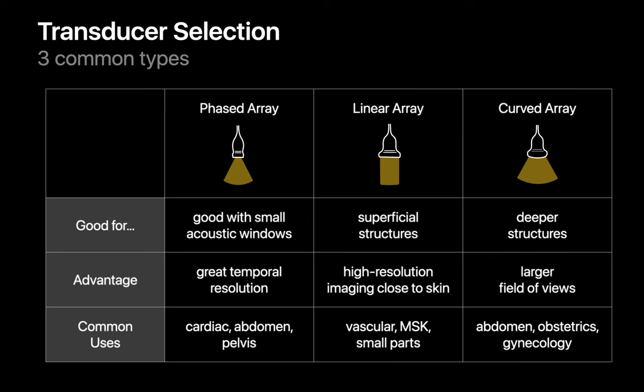Curved array transducers resemble linear array transducers but provide a wide fan-shaped image that permits larger fields of view and imaging of deeper structures. While their field of view is superior to linear array transducers, their image resolution is lower. Curved array transducers are also commonly used in abdominal imaging, obstetrics, and gynecology.